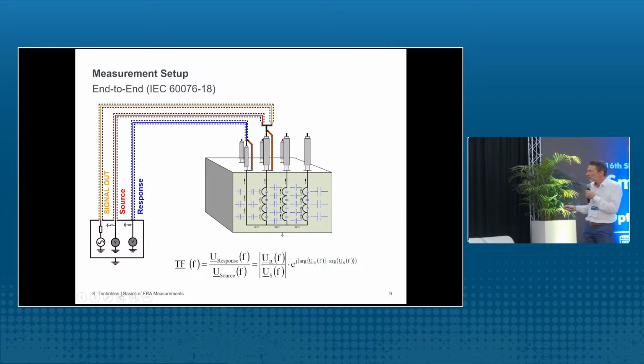This measuring equipment has a signal generator, so it generates sinusoidal voltages which are applied here to one end of the winding, and the other end here is the neutral, and we measure the response on the other end. We also measure the voltage at the connection point, at the bushing. Because of course we do not want to measure the frequency response of the signal line. Therefore we have to use a dedicated measuring cable for measuring the input voltage.